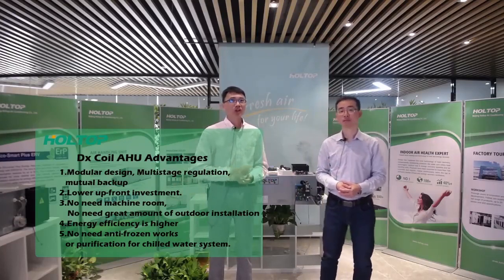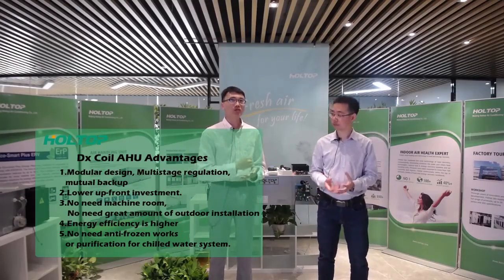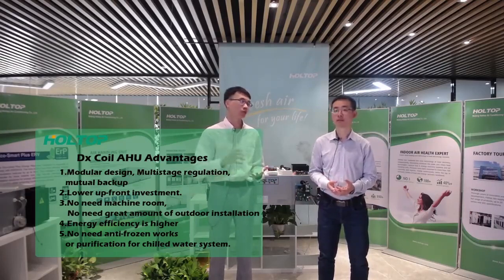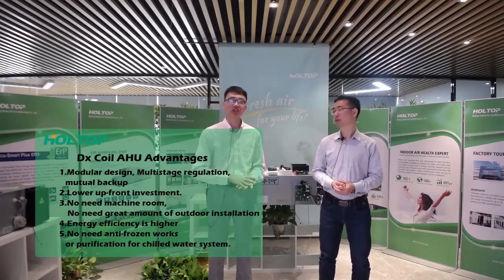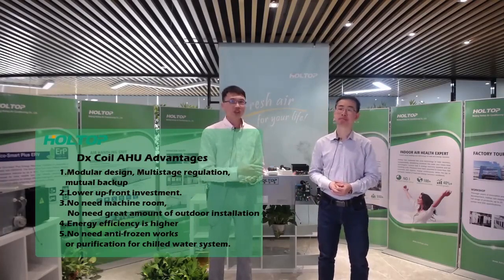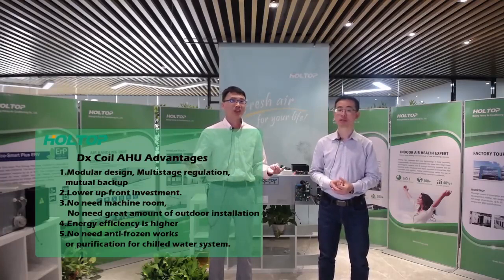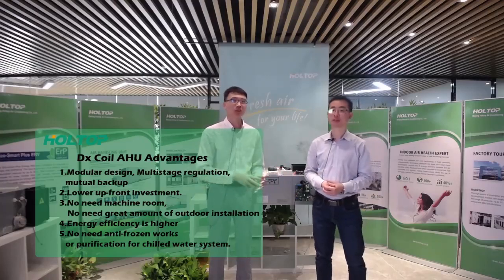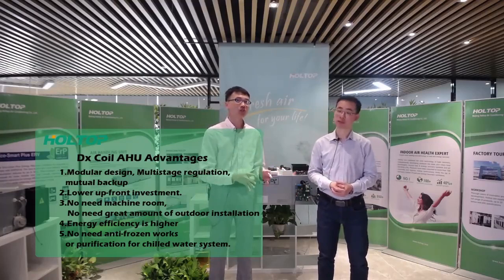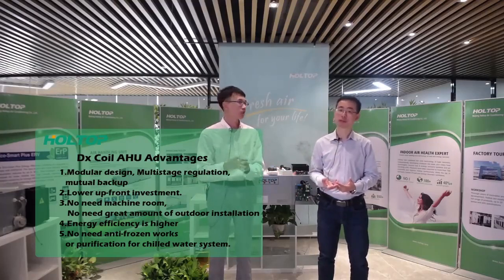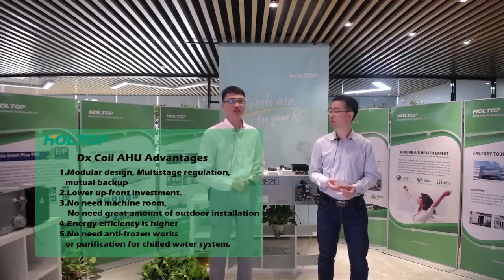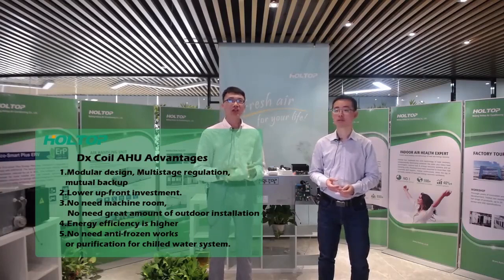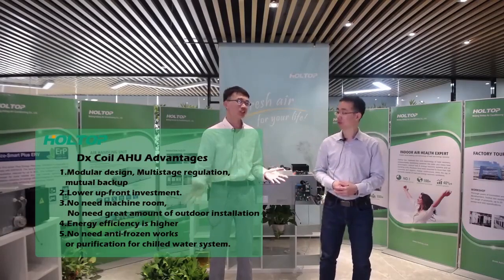And the last one, no need for anti-freeze works or water purification of the chilled water system. Now that there is no chilled water system in the unit system, users don't need to take any anti-freeze works or water filtration works for the chilled water system. So this will reduce the investment, the installation works, water consumption and maintenance costs. And this is extremely important to the countries and areas where clean water is not easily available.